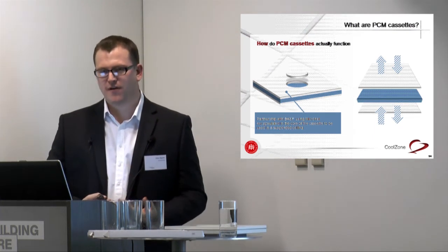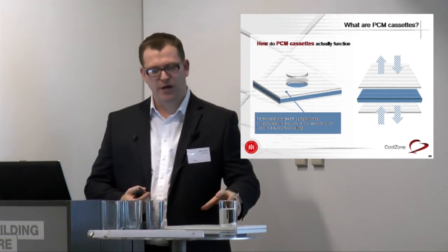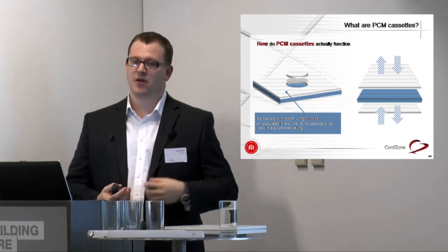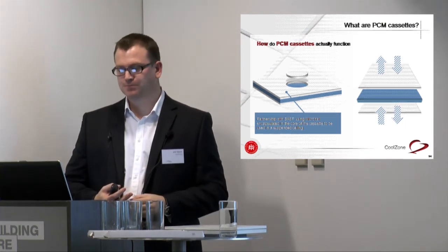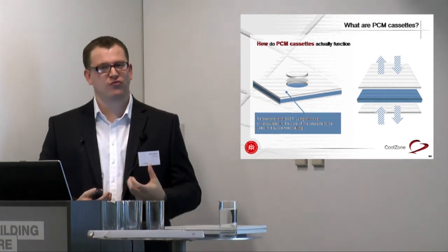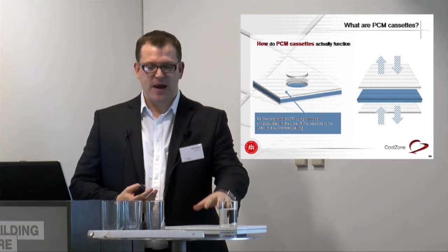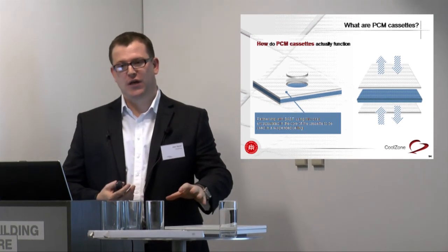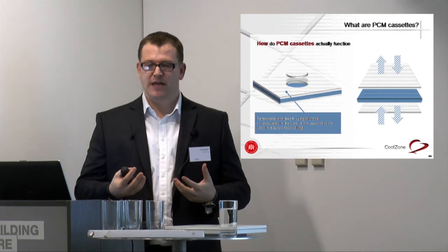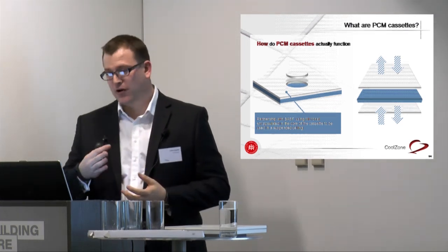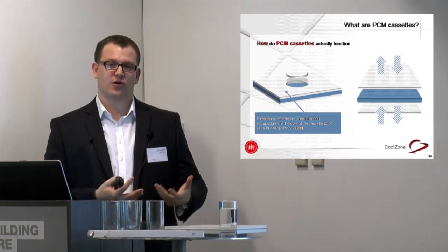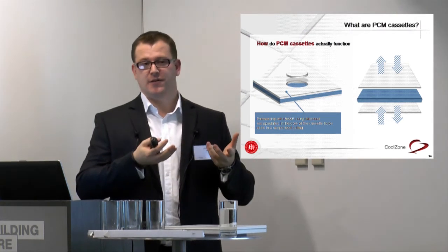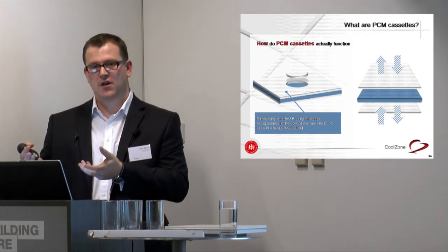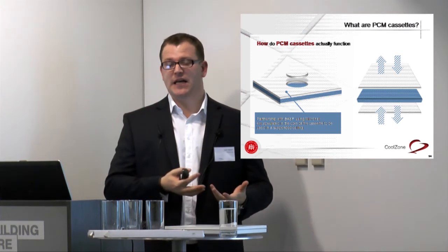I mentioned the fire reaction performance, which we achieve through the microencapsulation and by housing it in a metal ceiling tile. Because of that, we don't really want to cut the tiles; there's a benefit to keeping them as full tile units. If a room changes configuration or use and there's no longer an overheating issue, we can simply pick the tiles up and move them elsewhere, something you probably couldn't do with an air conditioning system.